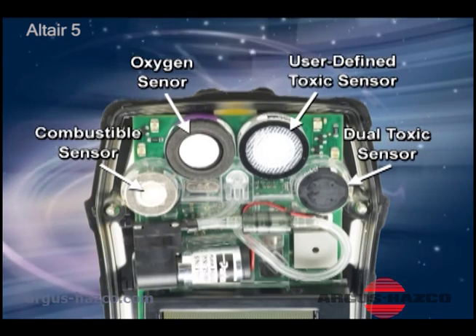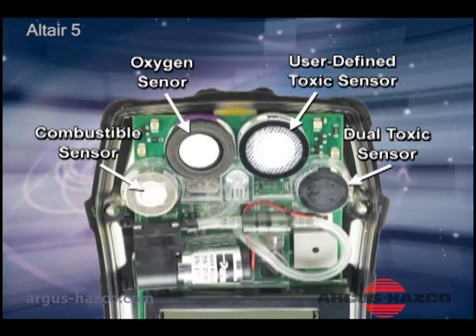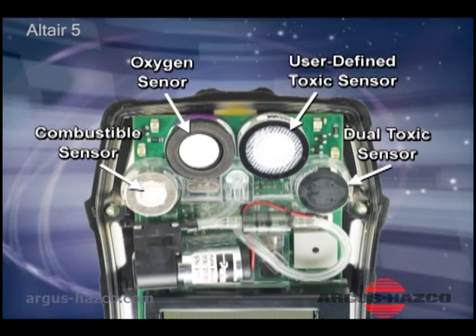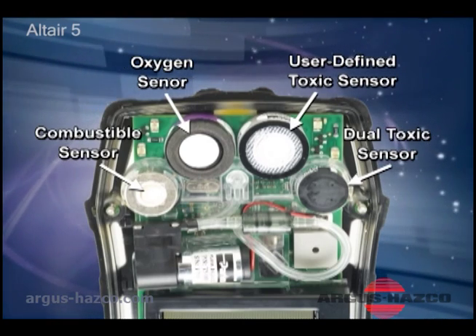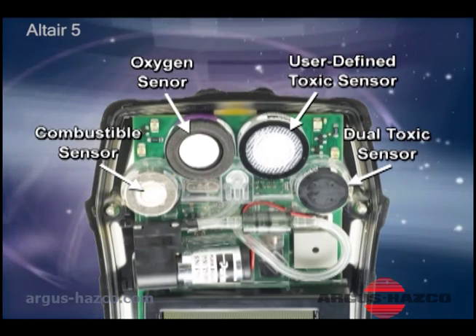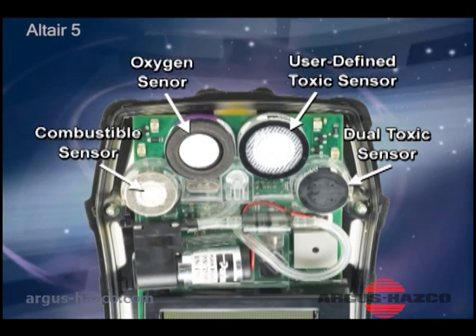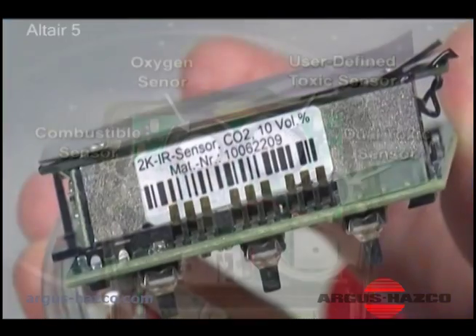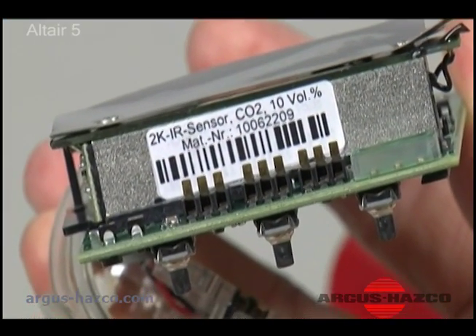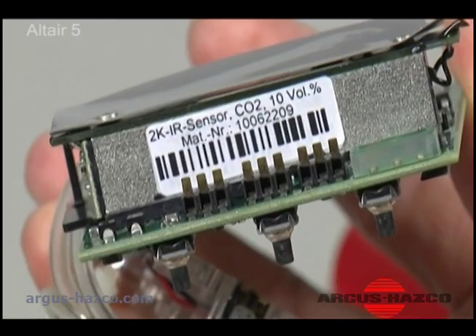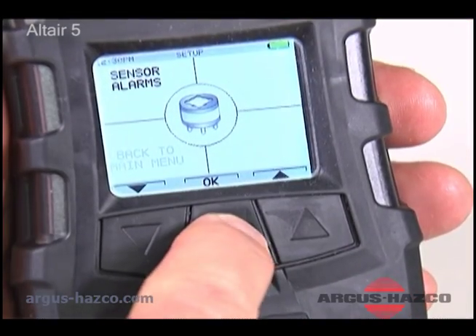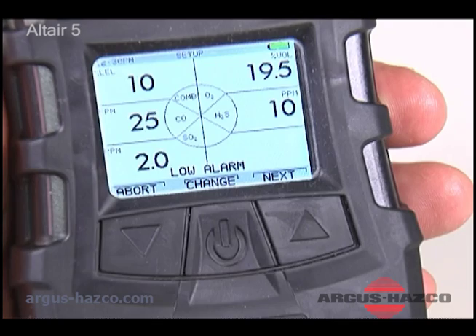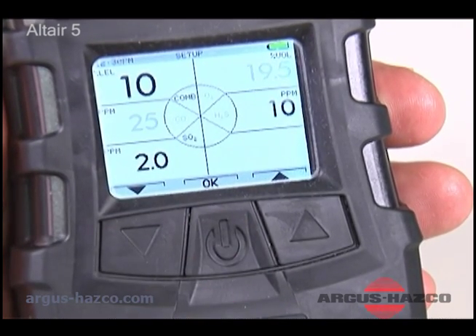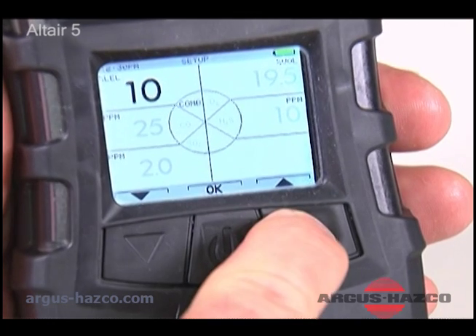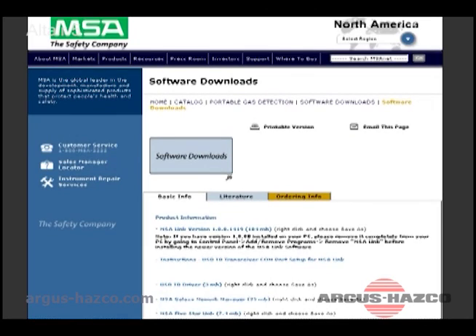The Altair 5 multi-gas monitor uses up to 5 gas sensors: a combustible gas sensor, an oxygen sensor, a user-defined toxic sensor. A dual toxic gas sensor detects both carbon monoxide and hydrogen sulfide, and an IR sensor, expanding the unit's capability to 6 hazardous gases. Alarm levels for individual gases are factory set. Use the Instrument Setup menu or MSA Link software to change alarm levels. Visit msanet.com to download the latest version.